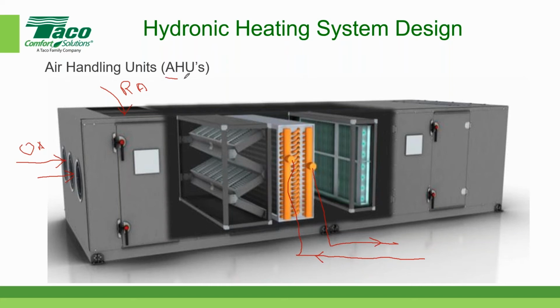And so that's very simple. As an air handling unit, hydronic air handling units usually have heating coils. We sometimes just label them as HC for heating coils. This one has a combination of heating coil and cooling coil, but I'm most interested today, since we're talking about hydronic heating, in the heating coil.